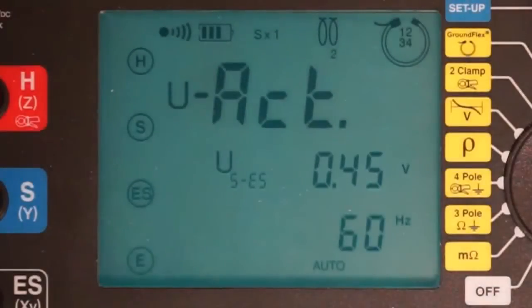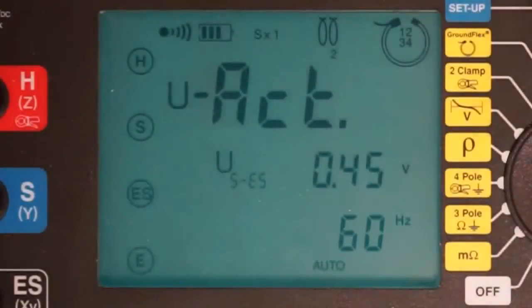If the measured voltage exceeds 0.1 volt, as our measurement does, this screen also shows the frequency of the detected voltage. This is the same as the frequency of the transmission lines, which in North America is usually 60 Hz. It is also common under some conditions for this to be 180 Hz in a 3-phase system.